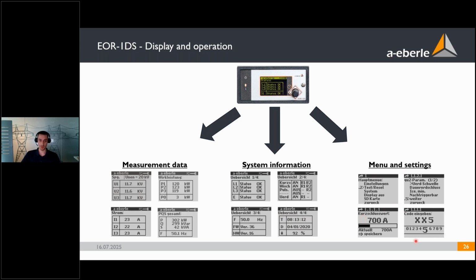And lastly, you have menu and settings where you can perform settings. Few examples would be to parameterize the QU2 method in this example, or set a threshold for short circuit indication, or change the device's code. You can put in a passcode for your device so that it can only be parameterized by someone who enters this passcode. So as you can see here, the display offers a variety of information slides while being really, really simple.